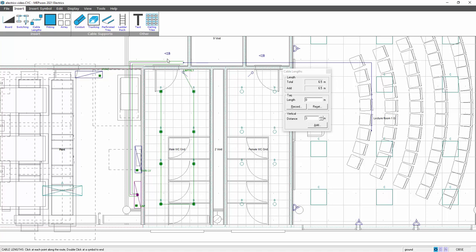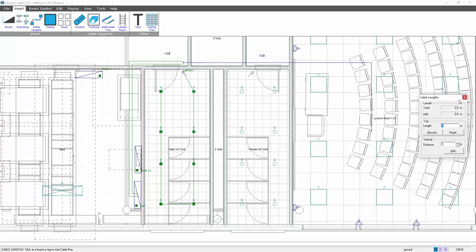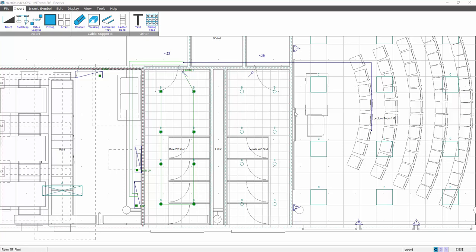So all I then do is follow the routing of the trunking and containment. I might then want to route up to my movement sensor because it's associated with this circuit, back on myself, across to here, and then double-click on the lighting switch. And that gives us a measured length, which is from the board via the containment, via the movement sensor to the switch of 8.2 metres, and a lighting length within the room of 10.7 metres. And then selecting OK.